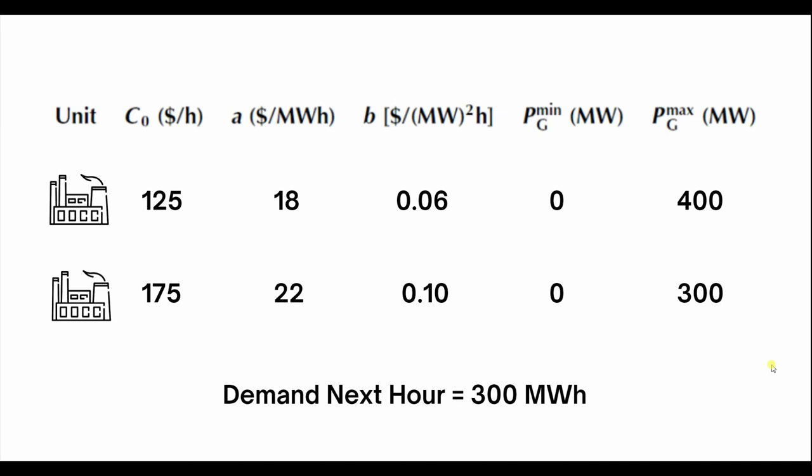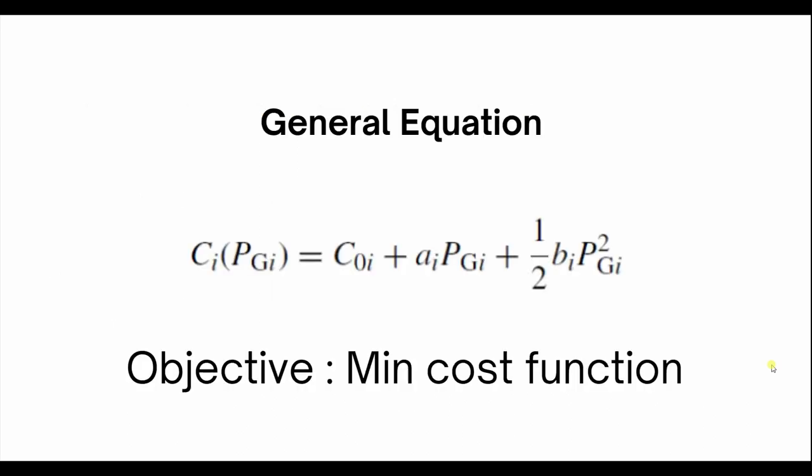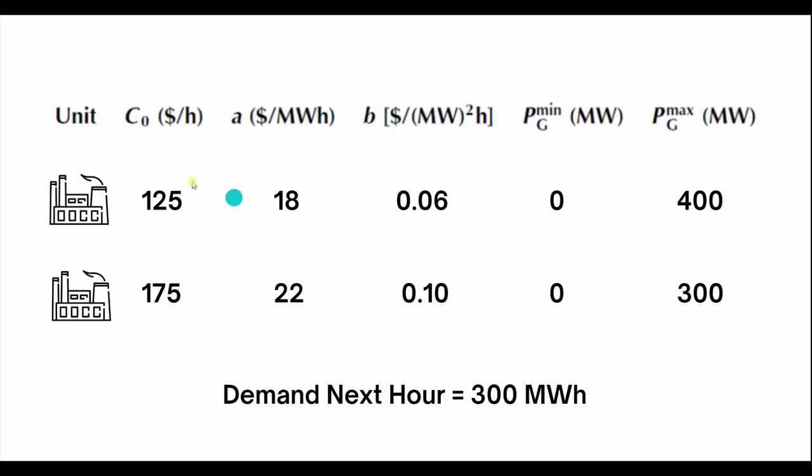The cost function, the constant cost function C naught of I, is 125 for the first one and 175 dollars per hour for the second power plant. Then a, which is also a constant, is $18 per megawatt hour and $22 per megawatt hour for the second power plant.